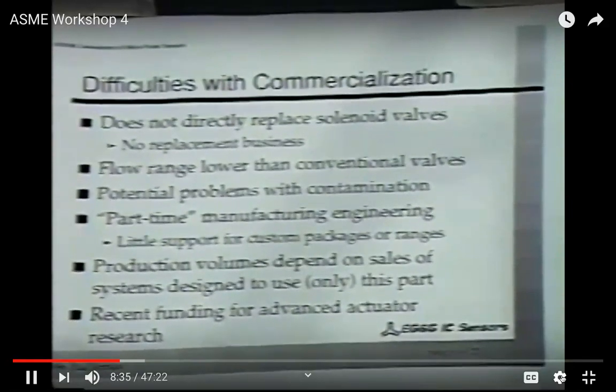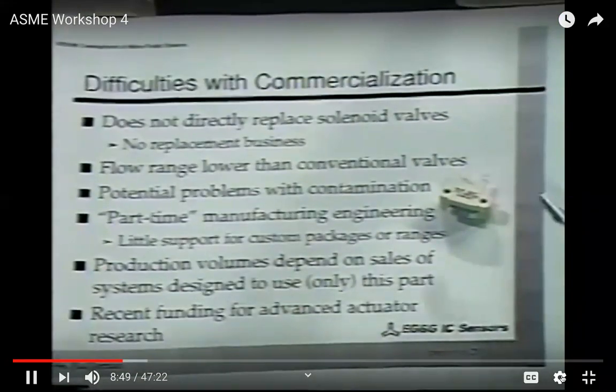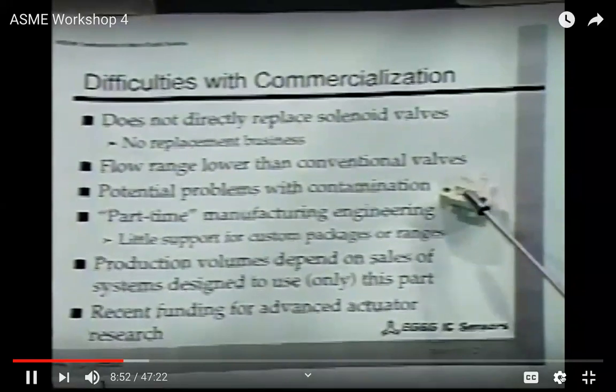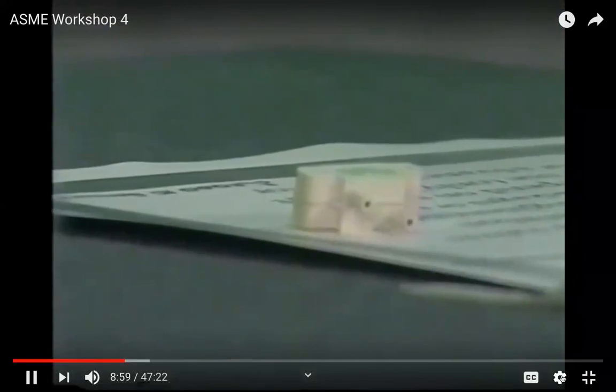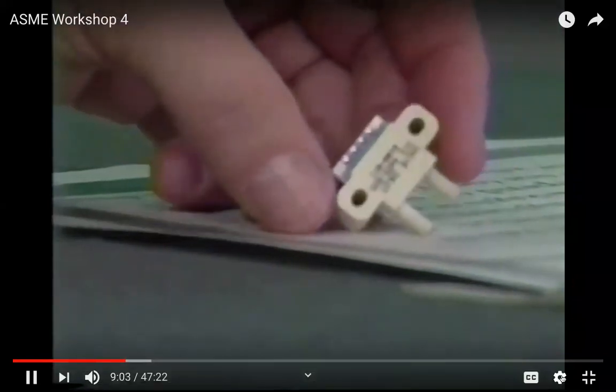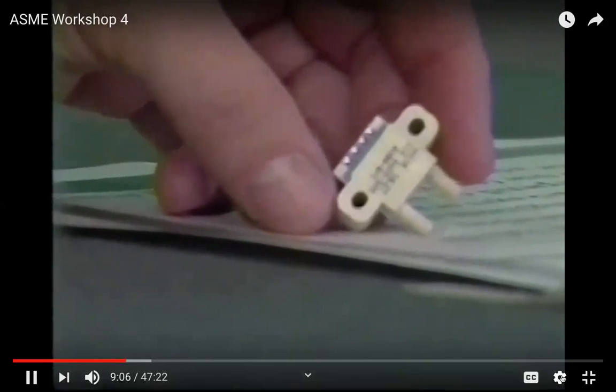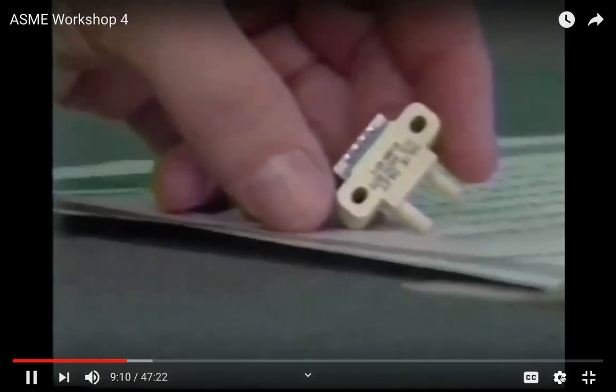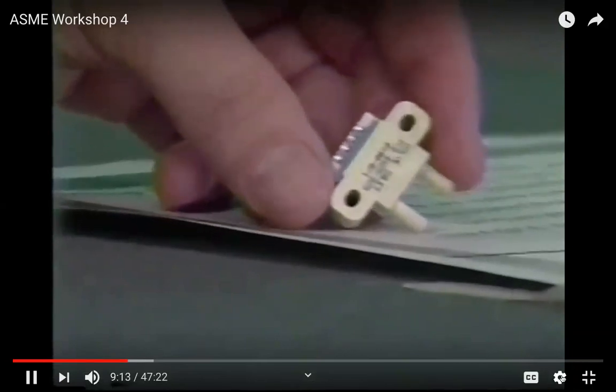We actually have a sample here. The part is currently packaged in this form, just to give you an idea of the size. We have the part mounted on a small ceramic base with a plastic cap, and we provide a stainless steel frit filter on the inside of that package. That frit has a nominal 5 micron pore size, so we filter out 5 micron particles and above within the package itself. But clearly the size scale of this part requires that the gases passed through it be relatively pure, or else you'll eventually clog the built-in filter.